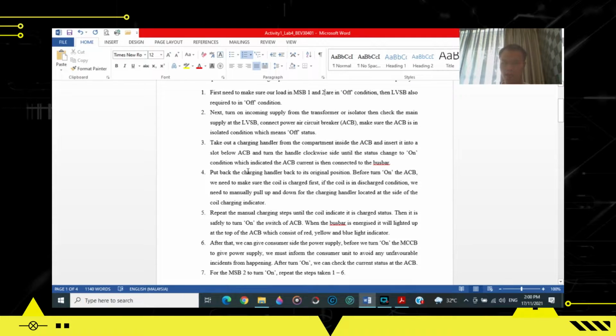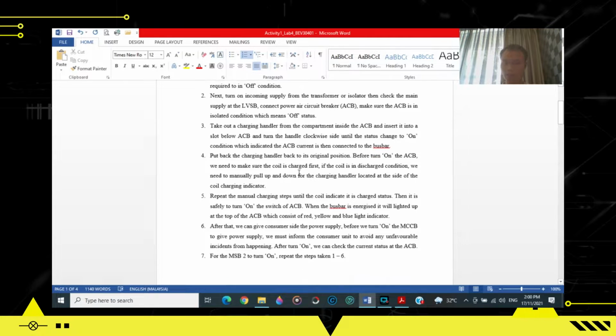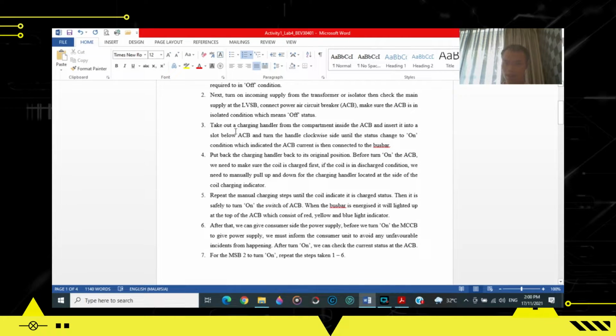supply and the LVSB. Well, this is to connect the power circuit breaker ACB. So we also need to make sure the ACB is in isolated condition with its off status. Thirdly, we are going to take out a charge handler for the compartment inside the ACB and set it to the slot. So we can turn the handle clockwise and change the status to the on conditions, which means that the ACB current is then connected to the bus bar. Then the bus bar will have the light indicator, which consists of a red, yellow, and a blue. They will light up when there's a current flow.